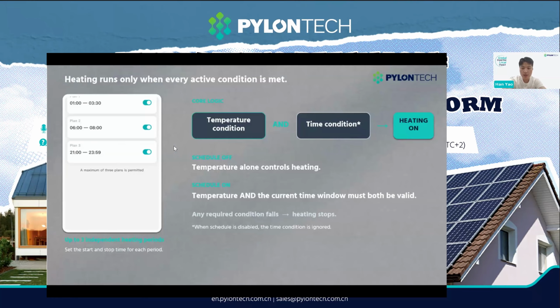And as you can see, the user can also set up to 3 heating periods. Here is a key value. Heating runs only when every active condition is met. If no schedule is active, temperature alone controls the heating. If a schedule is active, both the temperature condition and the time window must be correct. If either condition fails, heating stops. This gives the customer control without making the system difficult to use. The logic is very clear and designed to avoid unnecessary heating.